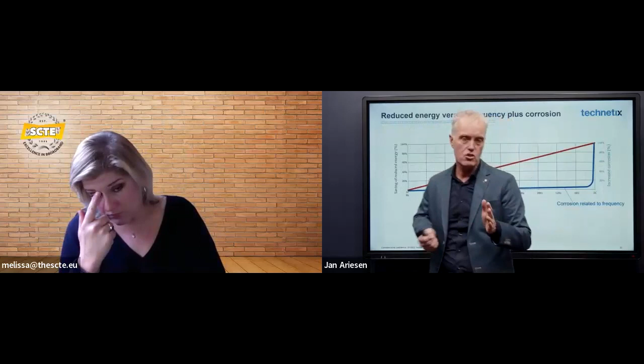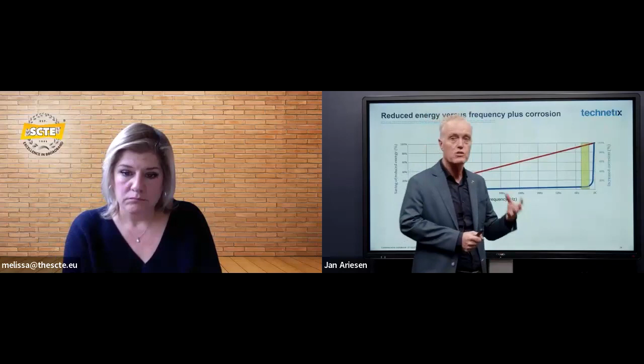Based on that, we came to the conclusion that probably this area here is the sweet spot, because we still have 95% of our saving while we have no impact of corrosion. So around 2.5 to 3 Hz is where the sweet spot is. Let's say 3 Hz, or 2.5 Hz in the Netherlands, will generate about 95% of the saving and has a very limited impact on corrosion. This is the frequency that we want to use now for our switched DC or low frequency AC, however you want to call it.